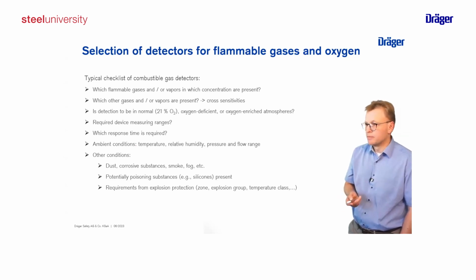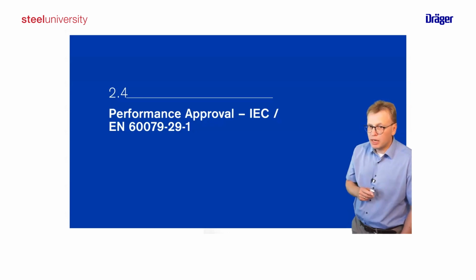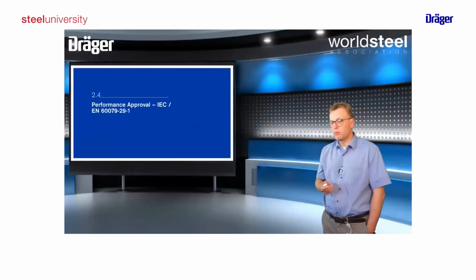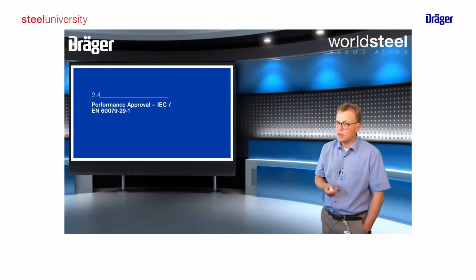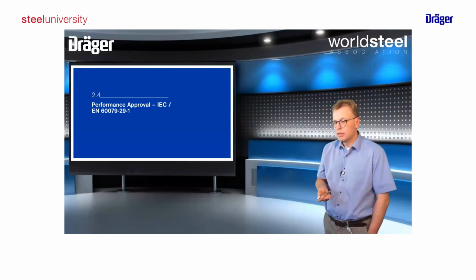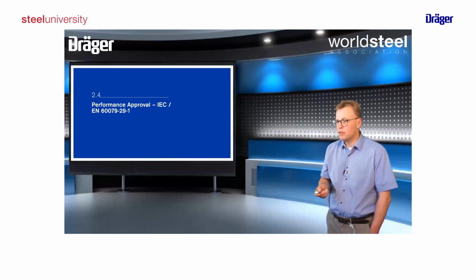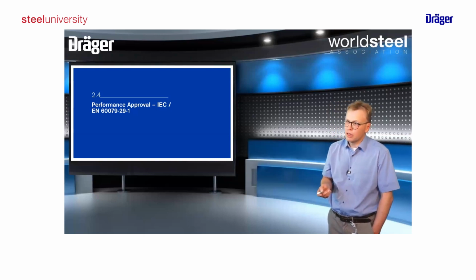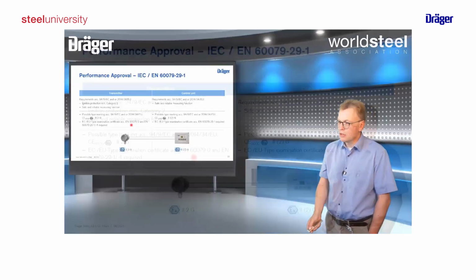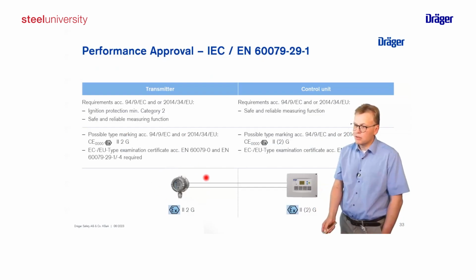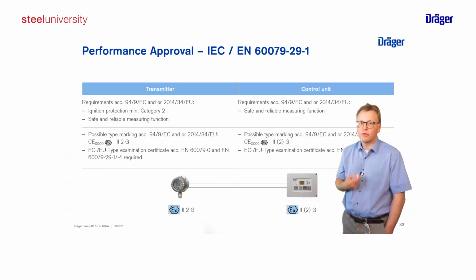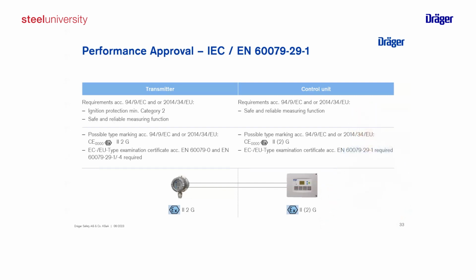Coming to the last part of my presentation, this is about performance. As I said, if you select equipment, and this is also written in the standards, we need to use reliable equipment. How can you identify this, and what is the performance approval looking at? We have two elements. On the one side, we have the detector in the field, in the hazardous area, and we have our control system. On the one side, we have the requirement for explosion protection. So the device needs to be certified and tested accordingly.